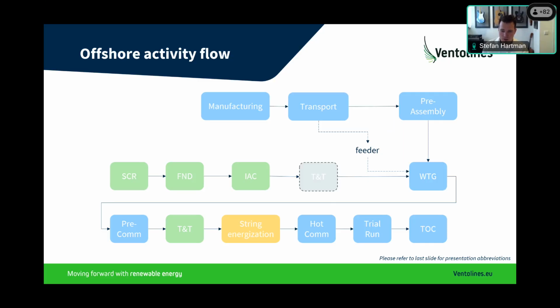Then the turbine contractor continues with pre-commissioning. We hand the stick back to the BOP contractor for termination and testing, then string energization by the employer. It goes back to the turbine contractor for hot commissioning, trial runs, and finally the takeover certificate, which will be issued per turbine.